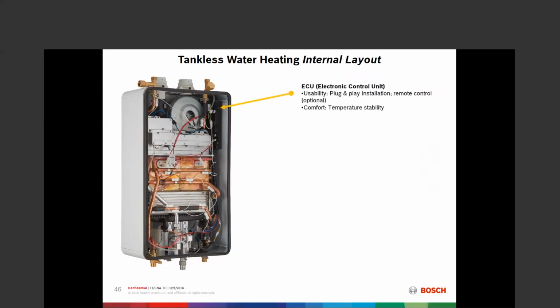Up here at the top, we have our ECU, our electronic control unit. That is where the OptiFlow combustion management system software lives, up there at the top on the right-hand side. It drives the fan for modulation. Again, the fan is driven by an ECM, an electronically commutated motor. And it's also managing the gas. The gas flow is managed down here via a positive pressure gas valve.